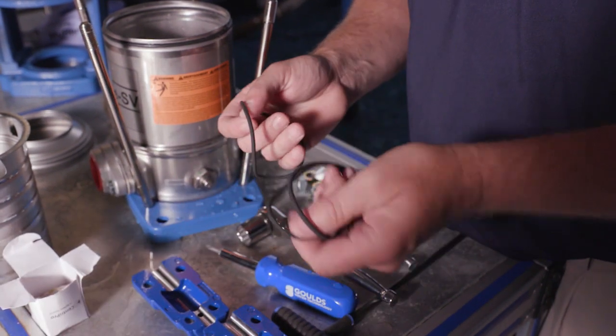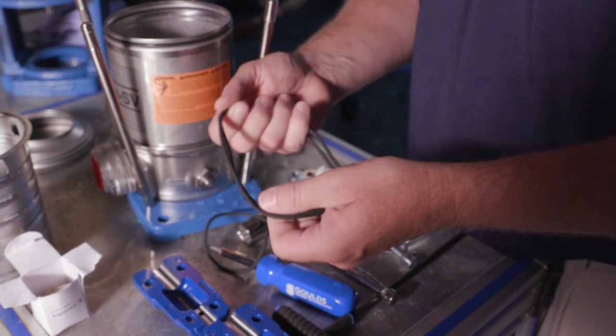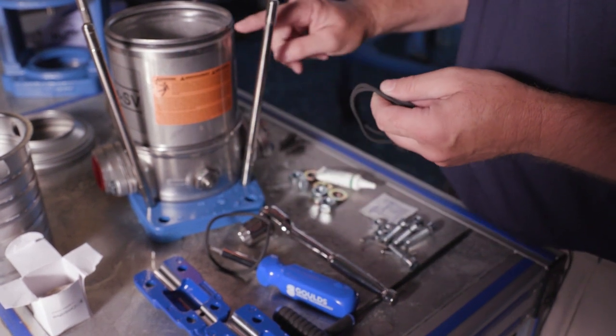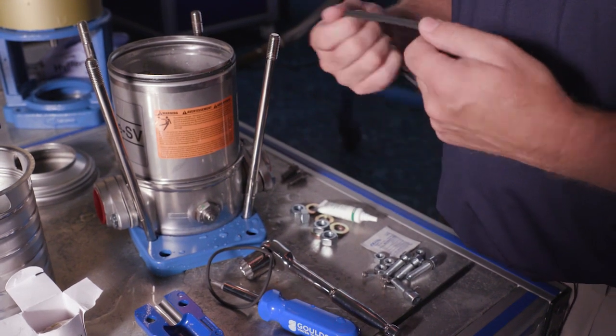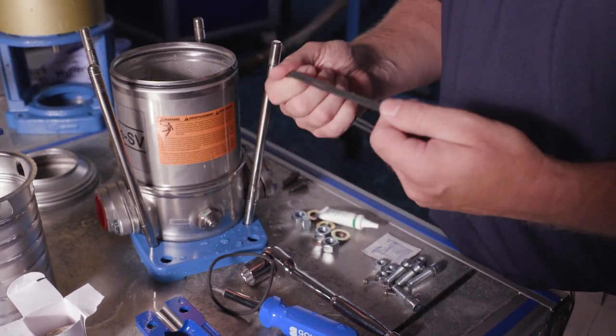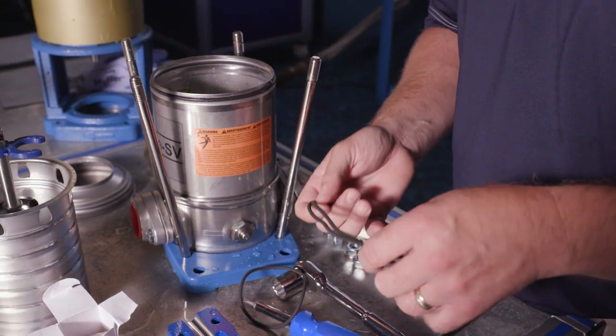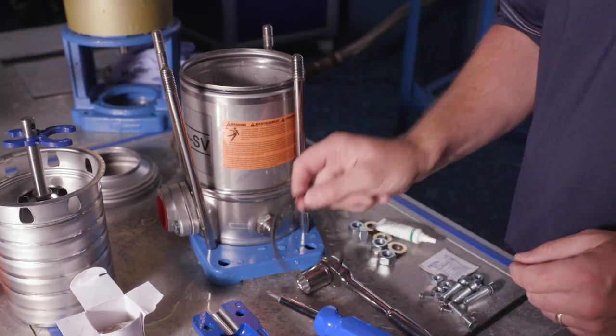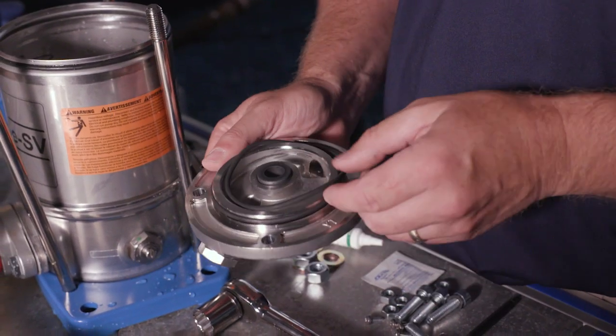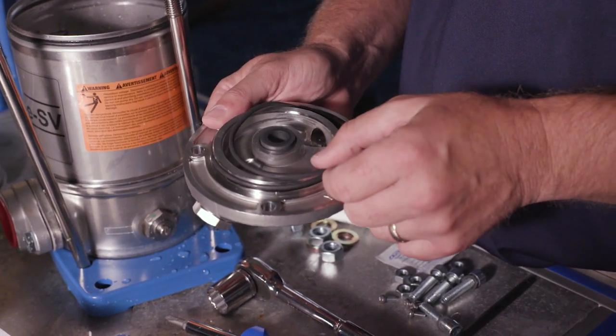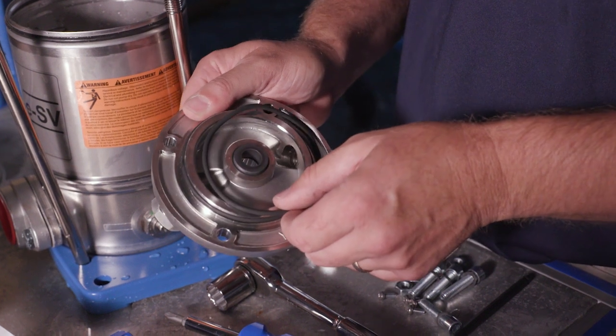Let's talk about the O-rings. We have two O-rings here, and these are your casing O-rings, one top, one bottom. Good idea just to use new ones. Notice the third O-ring is smaller, and that is for your seal gland seal plate here. Go ahead and put your new O-ring on your seal gland or seal plate.